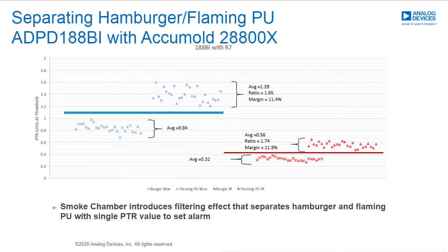This plot further illustrates that point, zeroing in on those two specific types of smoke, the hamburger versus the flaming poly, which has the closest PTR to the hamburger. On the left you have the blue response, on the right you have the infrared response, and this is using our ADPD-188BI module along with our chamber. It shows a little better than 10% margin, where you can set your threshold to not trigger on the hamburger smoke, but still trigger for any of the other valid smokes.